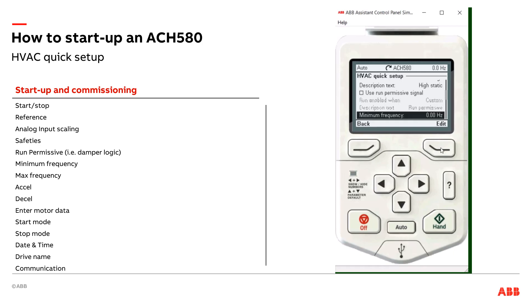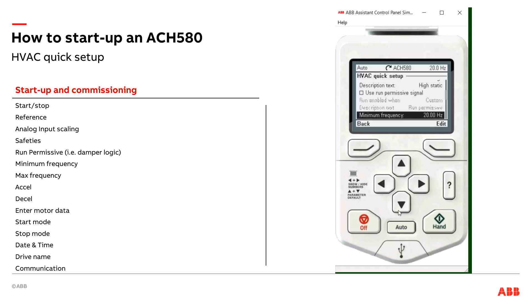I've got my minimum frequency. Say I've got a fan application and I don't want to go below 20 hertz — I can go in there and save that at 20 hertz. For maximum frequency, I'm going to leave that at the default 60 hertz. But if I had a certain fan array design, maybe I want to bump that up to 70, 72, or 75 hertz depending on the air handler design. Or if my test and balance guy didn't want me to go above, say, 57 hertz, I could limit it right there.